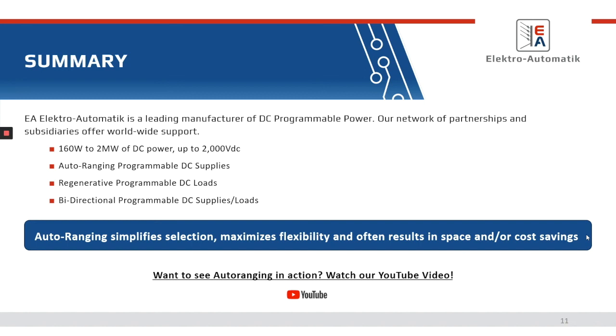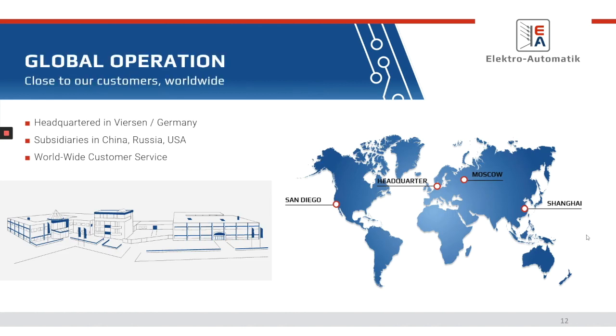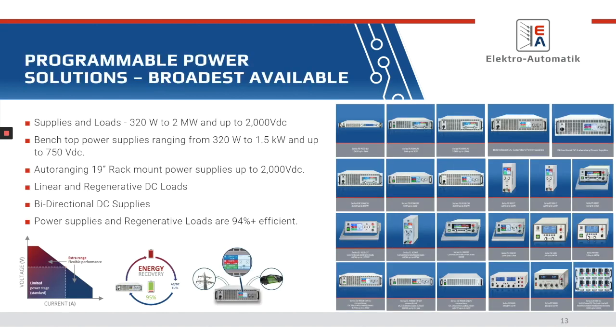Just a little bit about EA Elektro Automatik. We are headquartered out of Viersen, Germany. All of our manufacturing is done in Germany, and we have subsidiaries across the world for worldwide customer support. We manufacture and design power supplies and loads from 320 watts up through 2 megawatts of power, up to 2000 volts DC. All of our power supplies are auto ranging. We do not offer any square operating curve power supplies. We offer both linear and regenerative DC loads, bidirectional power supplies, and industry leading efficiency, up to 94+% efficient on all of our regenerative loads and power supplies.